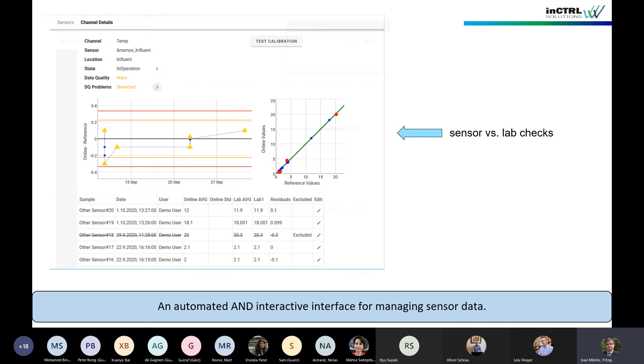You also have diagnostics that you would want to look at, for example, to see if you have enough data points, where the data points are being collected, at what sort of range or spread across the sensor measurement window, and how this compares to the lab, to see if there's anything deviating that might indicate you would need to recalibrate your sensors or clean them, or give you an indication that the operation is degrading.